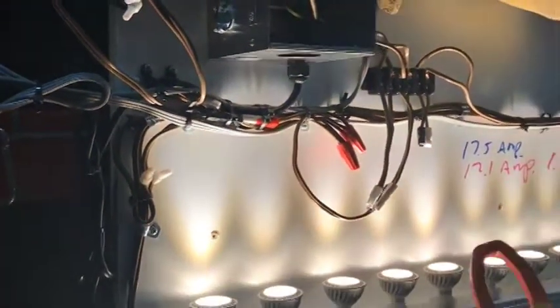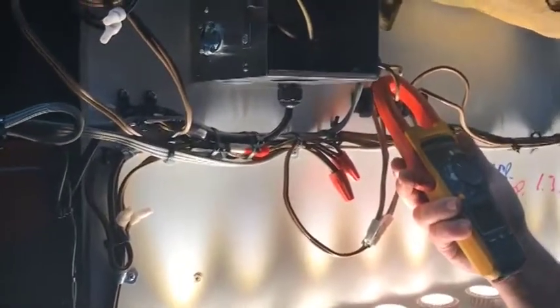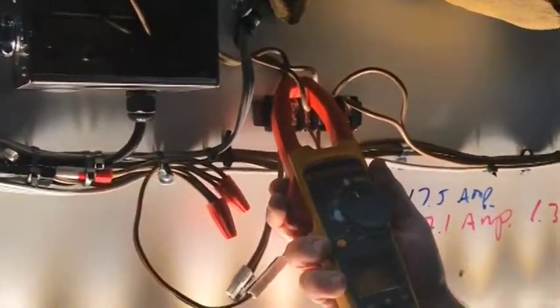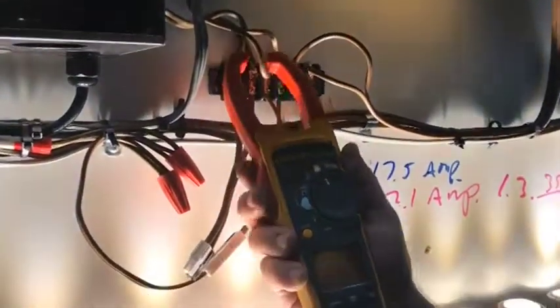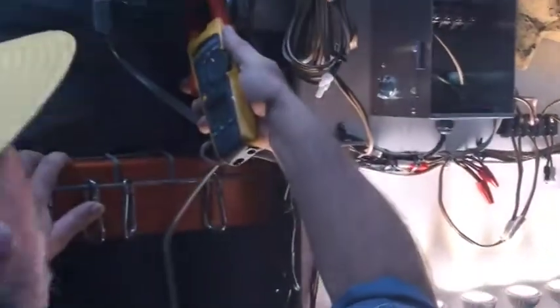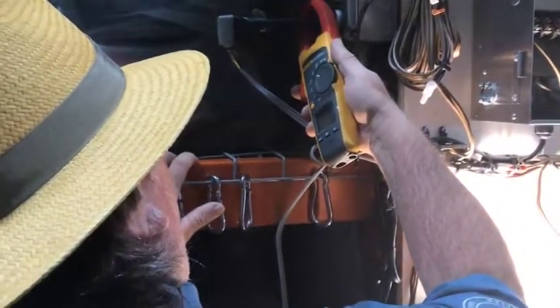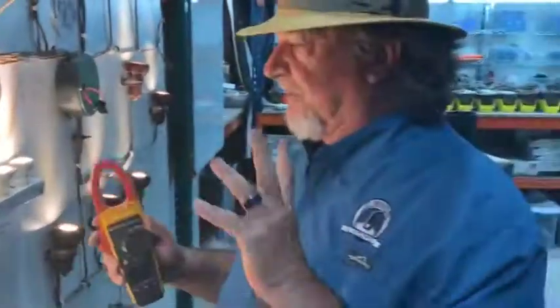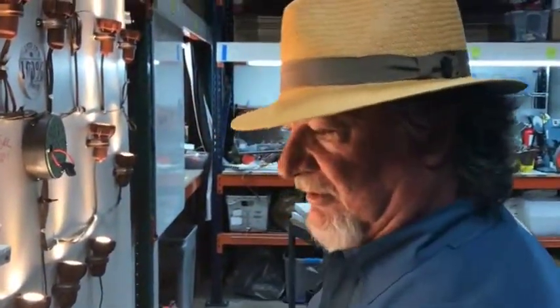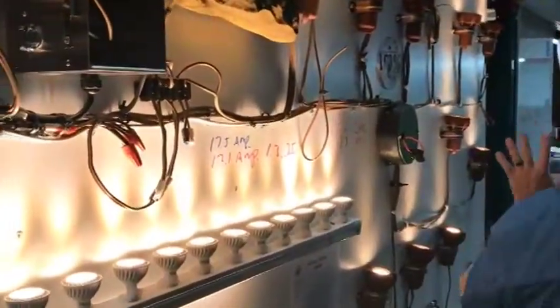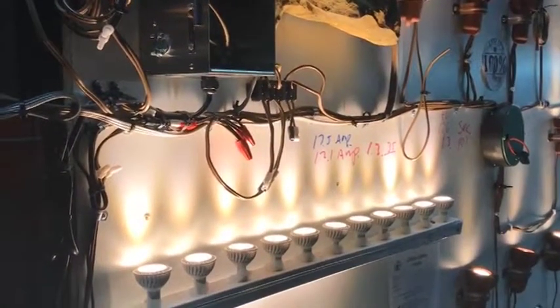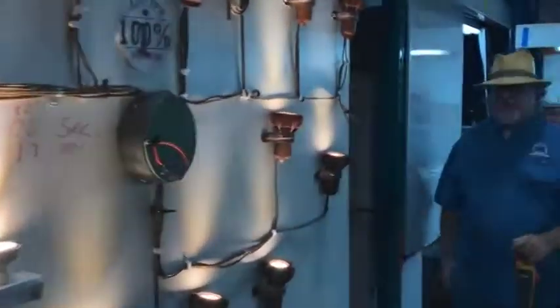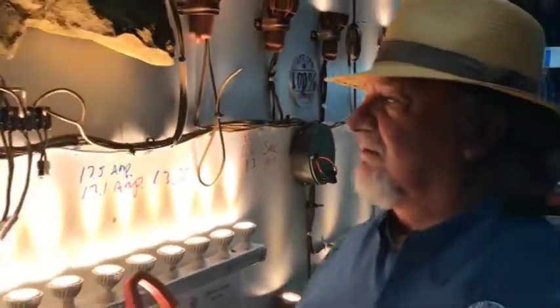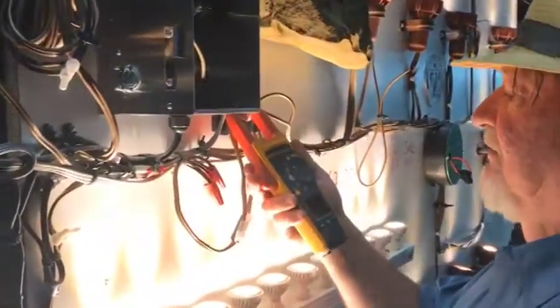So I've overloaded this, and if I take an amperage reading right here, I have 10.4 amps on it. I come over to here, and I got 1.1. All right, so I know just by doing the math, I shouldn't have that many. So if I come over here and I disconnect all these other fixtures back down to 28, right? So now, this is pretty interesting.